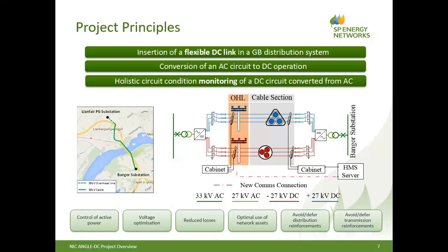You can see further down there the voltages that we're going to operate it at, so it will be plus or minus 27 kV DC, and there's a few boxes at the bottom of that slide which just illustrate the benefits. It will give us control of active power. We'll be able to optimize voltage, reduce losses by controlling the power flows, and obviously use the assets better because of the increase in capacity it gives us operating at DC rather than AC, and hopefully that will avoid or defer further reinforcement.